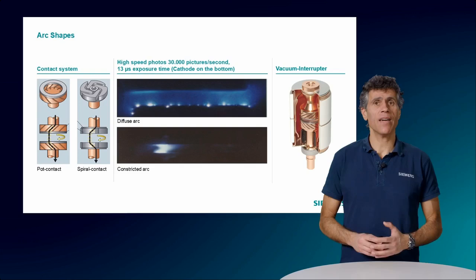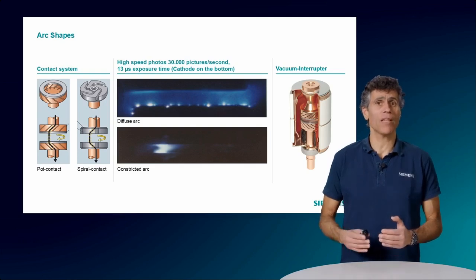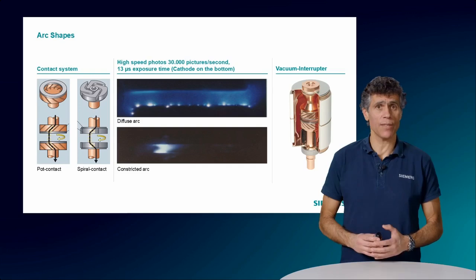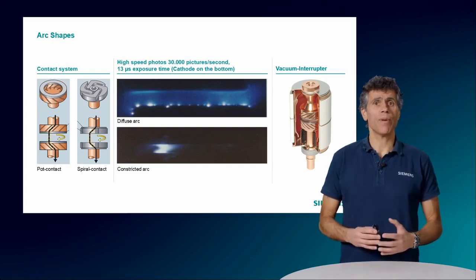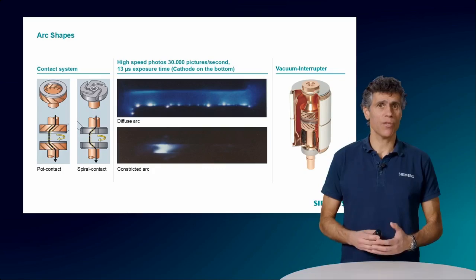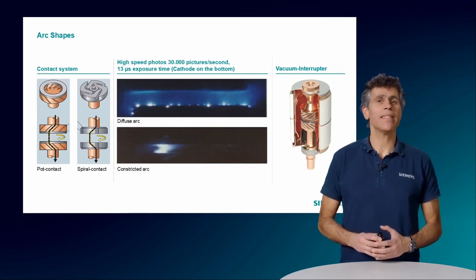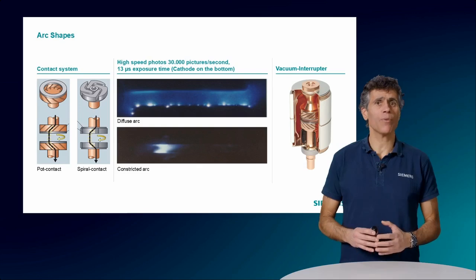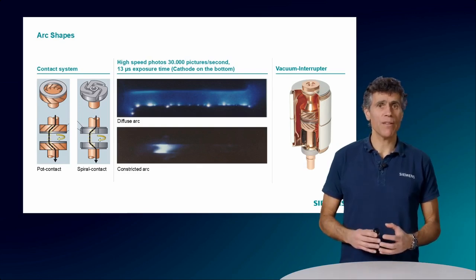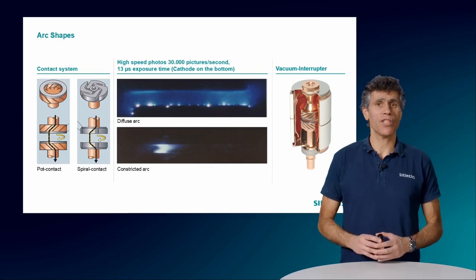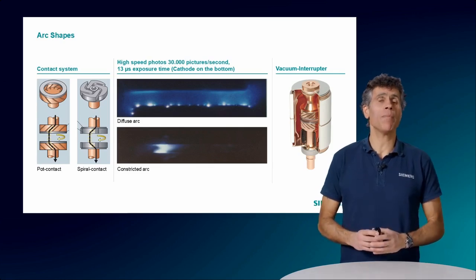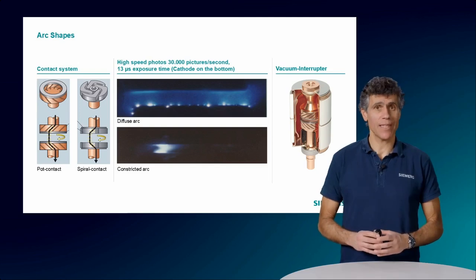The arc gets harder to control as higher voltage and more energy are available to feed it. The art of interrupting and connecting the energy, which is, as you will remember, the main function of the switchgear, is to make that in a smooth way that doesn't cause any harm. But there is no known way of doing that without a discharge taking place, particularly when high amounts of energy are involved. But don't underestimate the sparkle also with lower amounts of energy. Also inside those little switches at your apartment, sparkles and cooling down takes place.